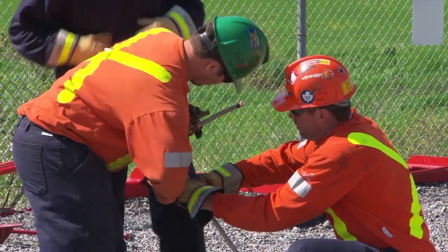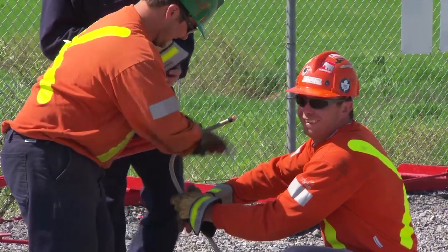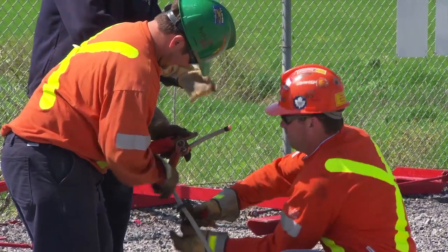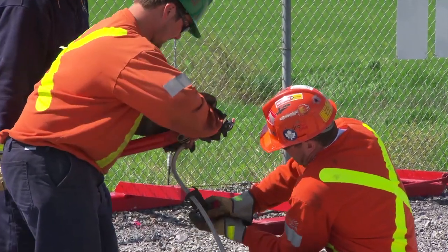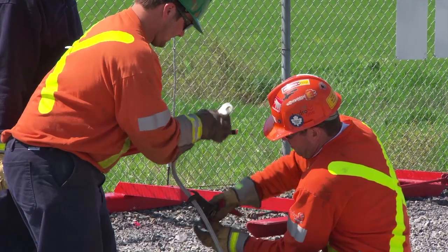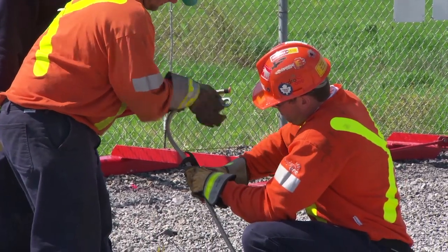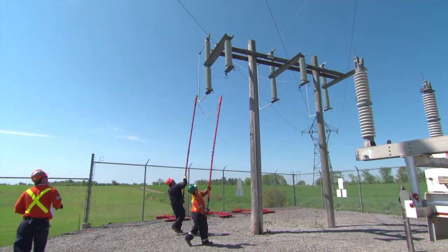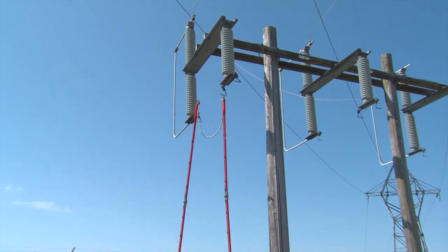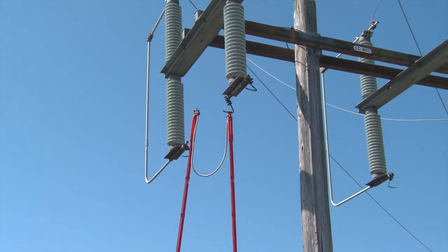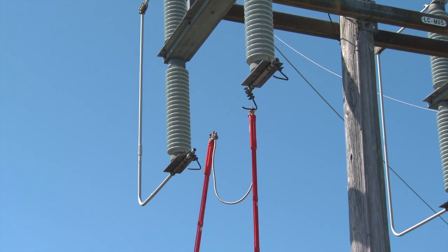If the station does not have pre-made LC-MUS jumpers, a hold-off on the 115 kV circuit will be required while test fitting and fabricating jumpers. These jumpers are required prior to starting the MUS switching. Once they have been fabricated and test fitted, remove the jumpers and store them on site.